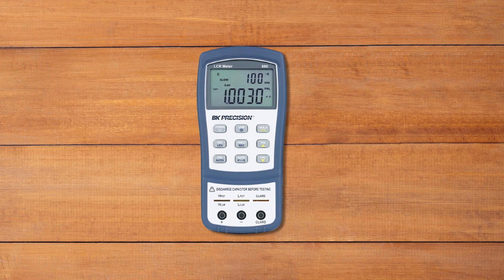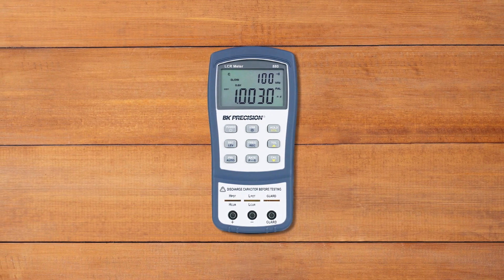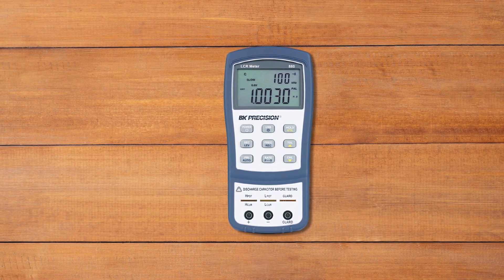The BK Precision 880 handheld LCR meter is a powerful and portable tool for measuring inductance, capacitance, and resistance up to 100kHz. With the 40,000-count primary screen, you can see even large values of the parameters — capacitance, inductance, and resistance. The second screen comes with a modest 10,000 counts, showing parameters such as dissipation factor, quality factor, DCR, ESR, and theta.